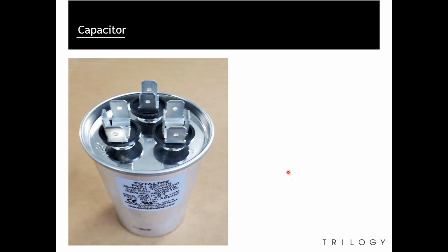Our capacitor. Now, again, if the compressor doesn't kick on or the fan doesn't kick on, chances are it's a simple capacitor, and it sends extra power to the compressor and the fan for the startup. So this is a very common problem that you see a lot. I probably go through 10 to 15 a season of these capacitors, a very common problem.